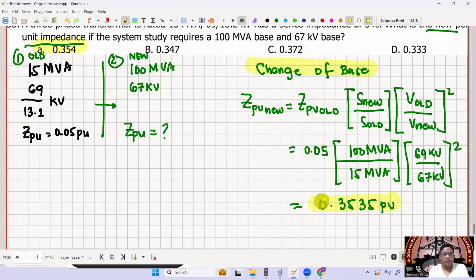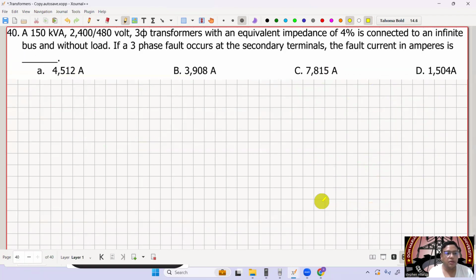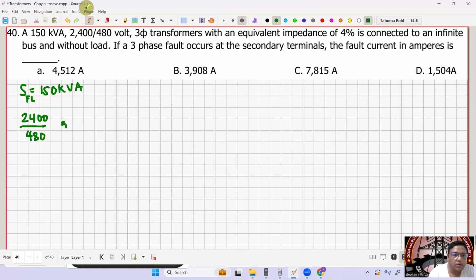Okay? So, unahin muna natin yung number 40 bago tayo pumunta sa number 39 kasi medyo mas mahirap yung problem doon for your transformer banking. Okay, so that's a problem for transformer banking kasi. So number 40, so we have a 150 kVA. So S is 150 kVA. So SFL yan. Then 2400 slash 480 volts. Three-phase transformer with equivalent impedance. So yung ating Z1 dito is equal to 0.04 per unit. And this is connected to an infinite bus and without load or unloaded yung transformer.